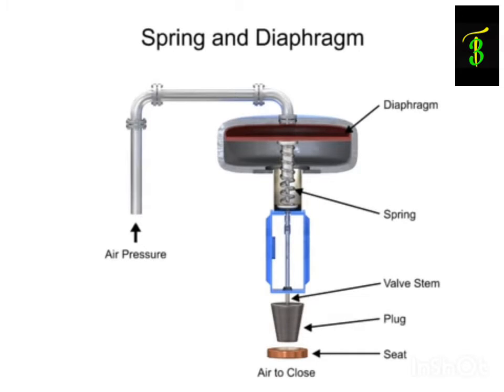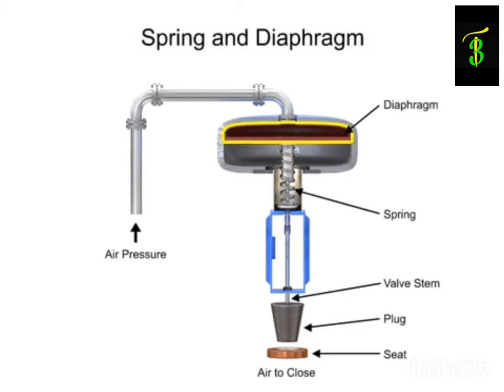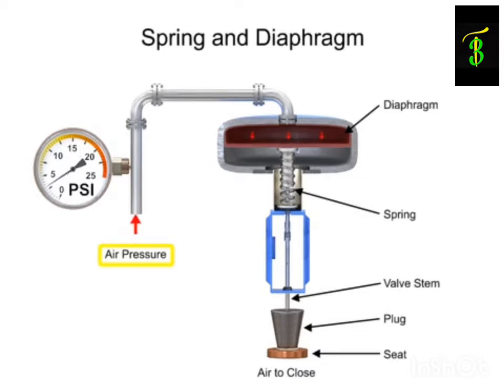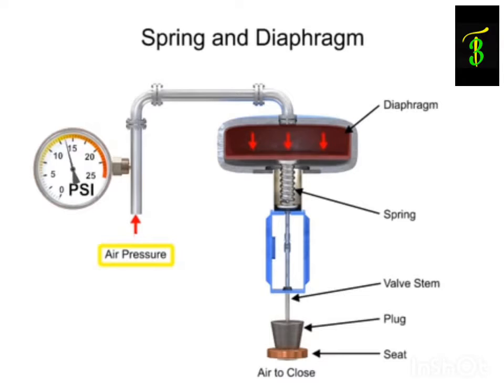As the name suggests, the spring and diaphragm actuator uses a spring and a diaphragm to move the valve stem and plug. A 15 psi pneumatic signal enters the housing at the top of the actuator. As pressure is exerted on the diaphragm, a downward force is applied against the spring which moves the restrictor. The diaphragm moves until it creates an equal but opposing force against the spring, at which time the motion stops as the plug meets the valve seat.